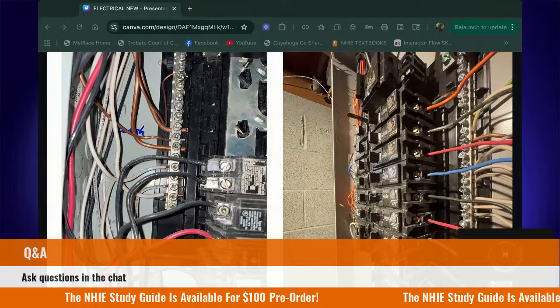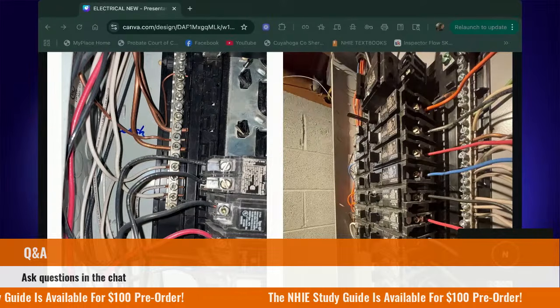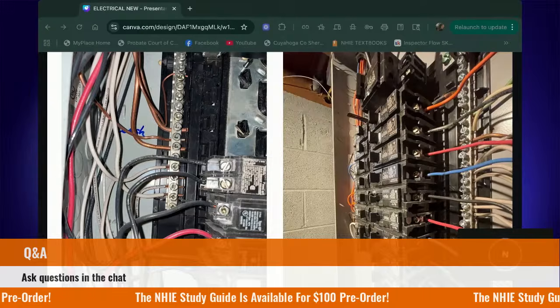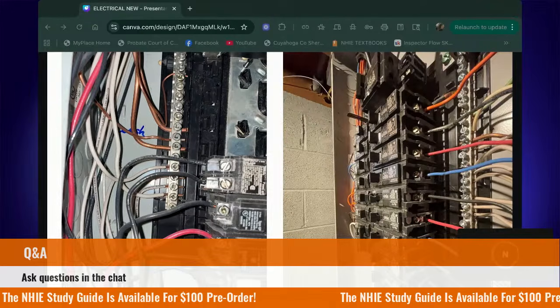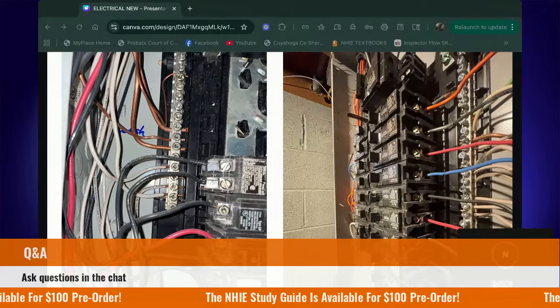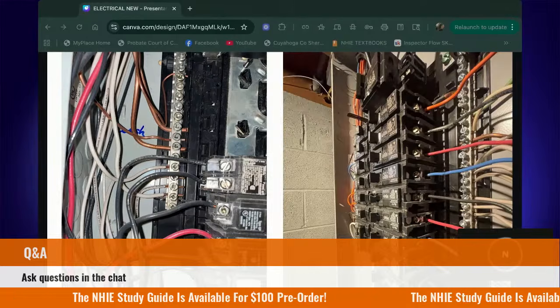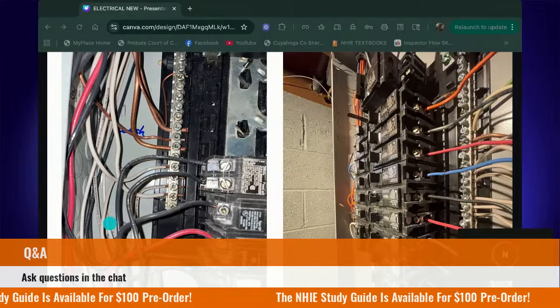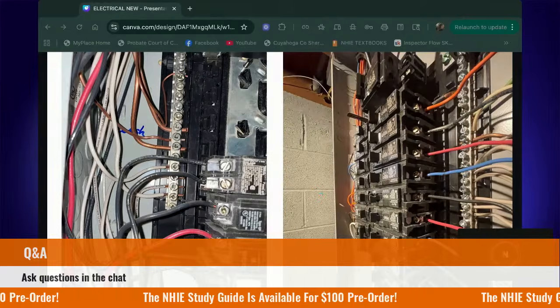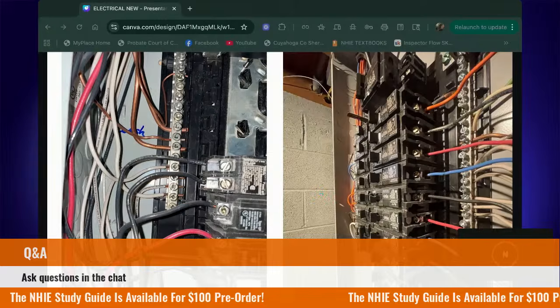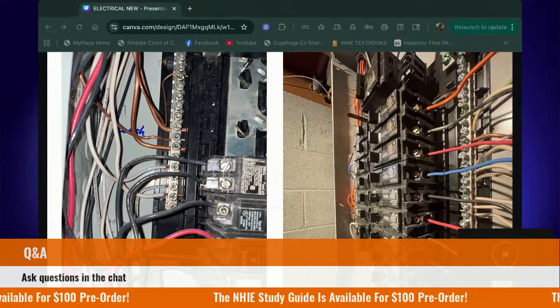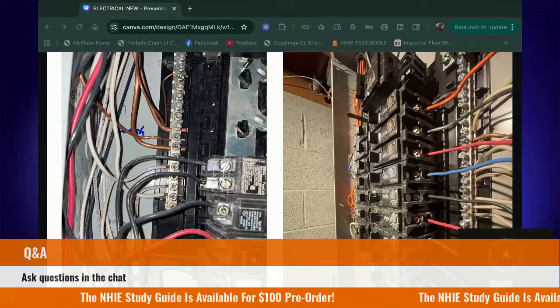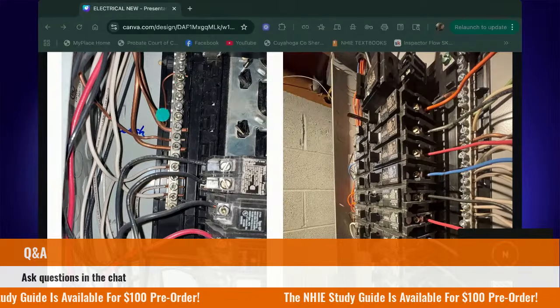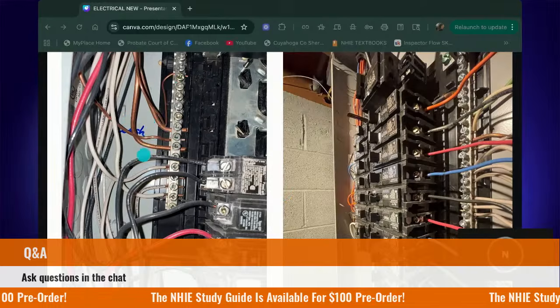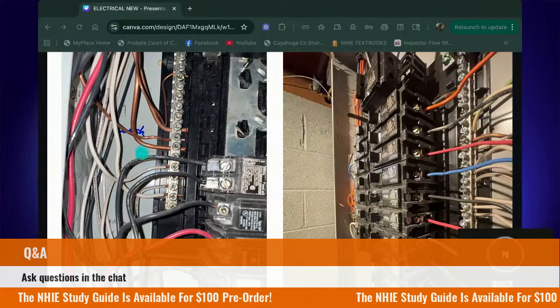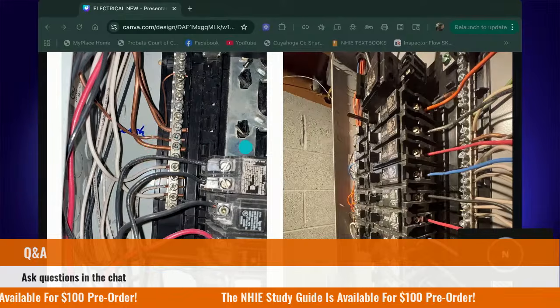No. Why not? Because the neutral returns the electricity to the source. That is true. And the grounded, which is the copper, right? Correct. That doesn't do the same thing. Hold on. This is my neutral bus bar. I've got ground wires, these bare copper wires. Remember you asked me earlier, what is bare copper? Literally just a bare copper wire. These represent our ground wires.